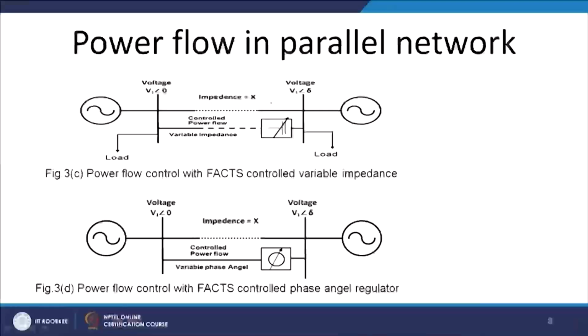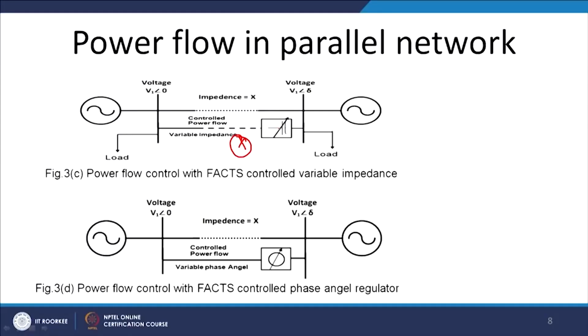In the same way we can go for the solution with FACTS devices also. Let there be an uncontrollable line, the upper one, which may be the old one. Now we can place a new controllable line with a FACTS device. So this is a variable impedance. This variable impedance can be controlled, so the x amount of power flowing through the lower line is controllable, and thus 1 minus x should be limited to the thermal limit and other limits.